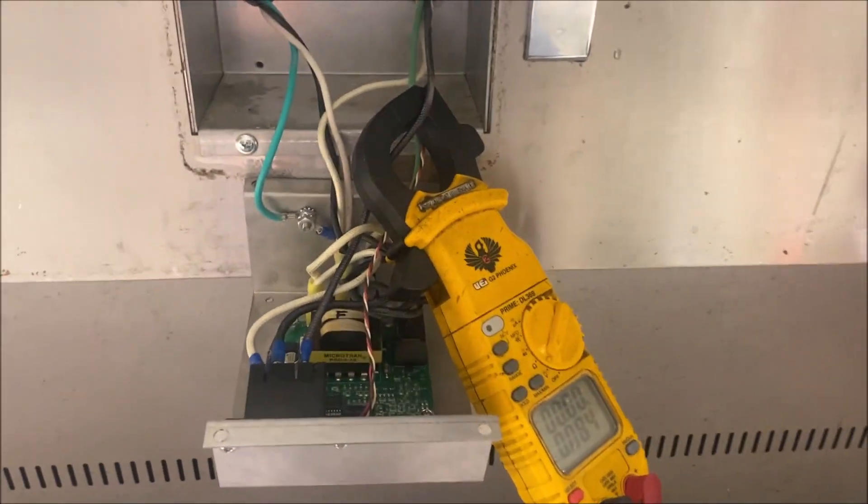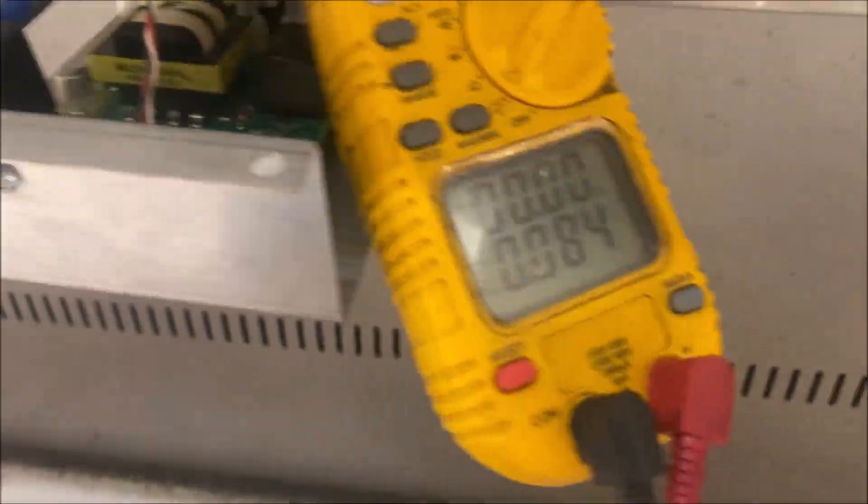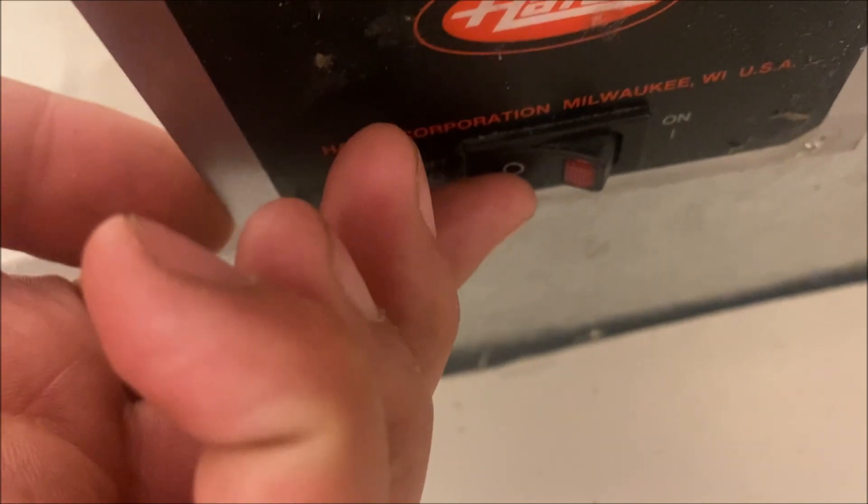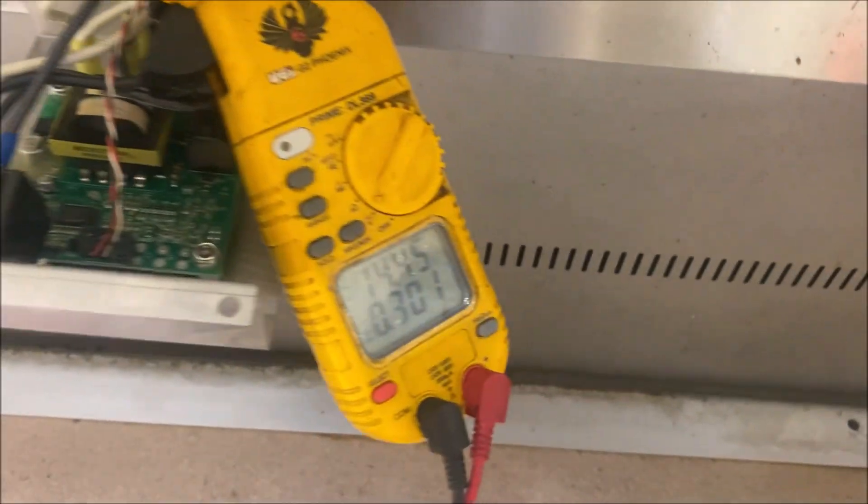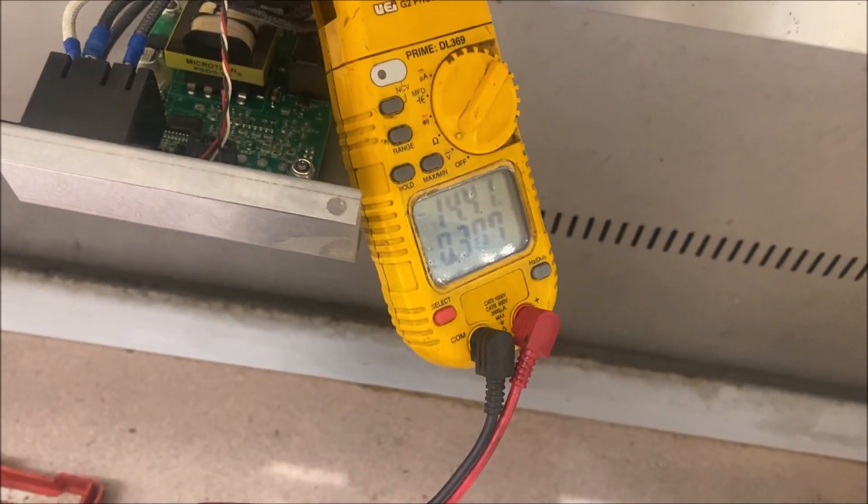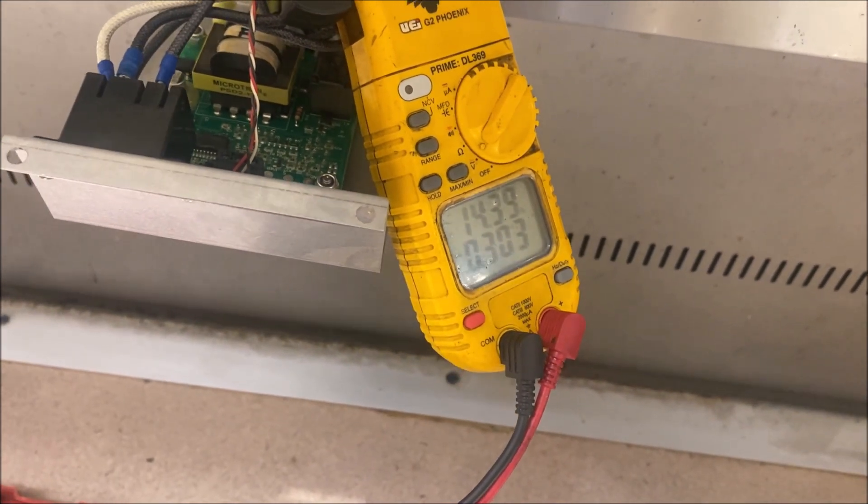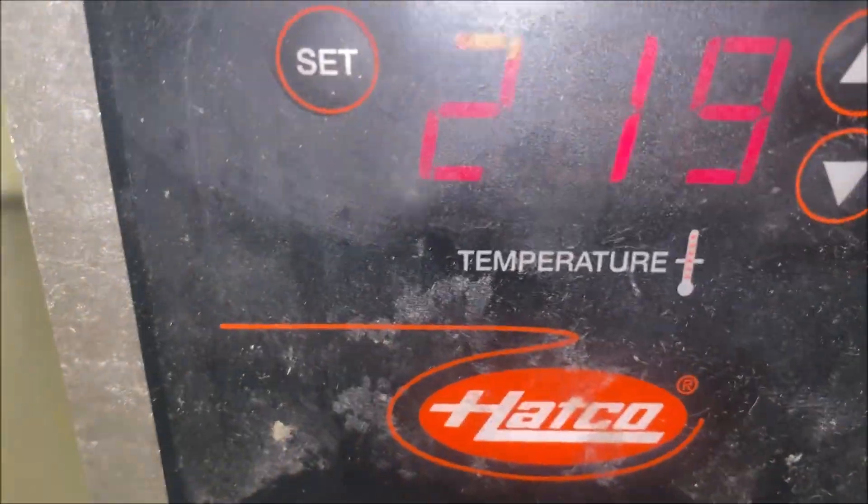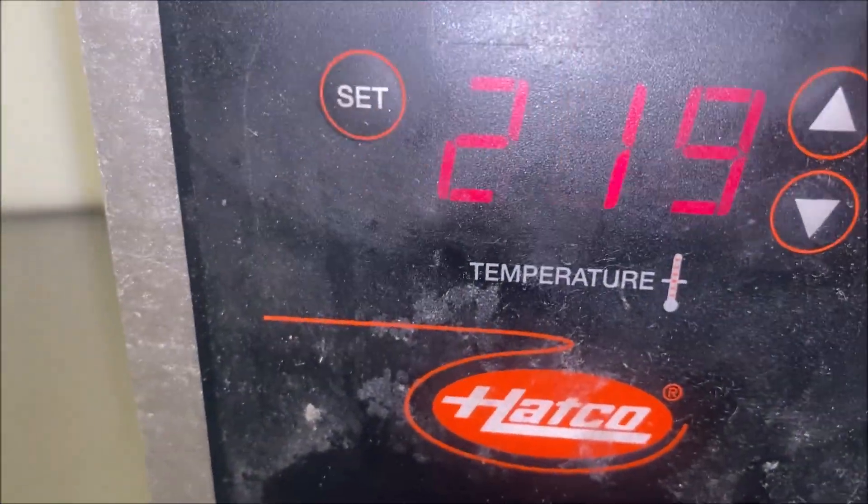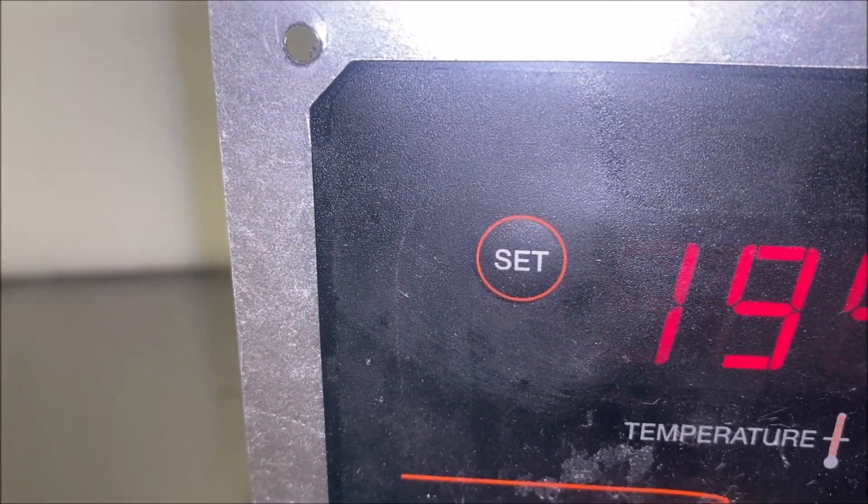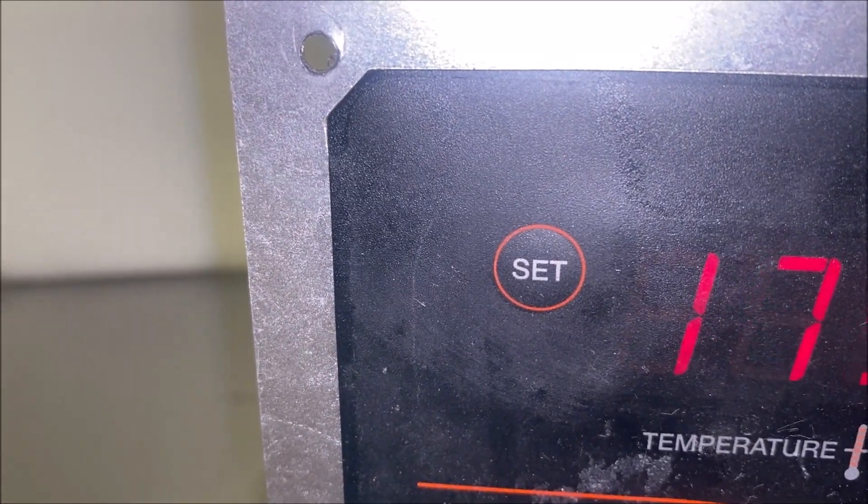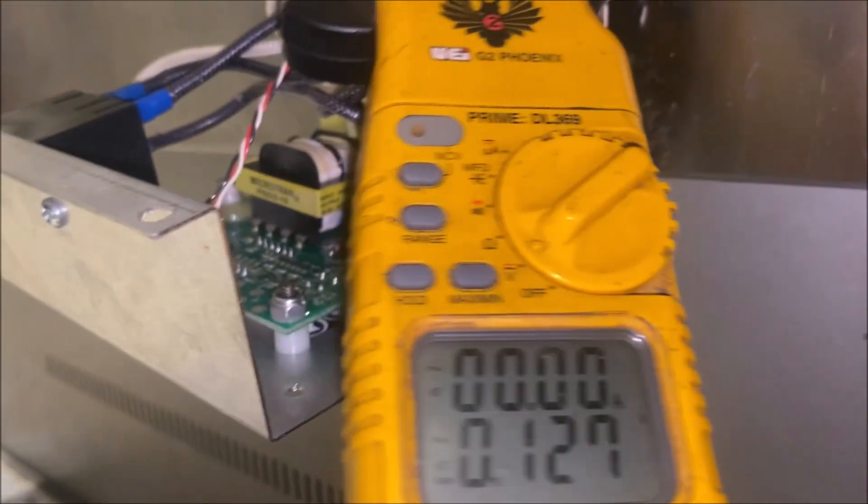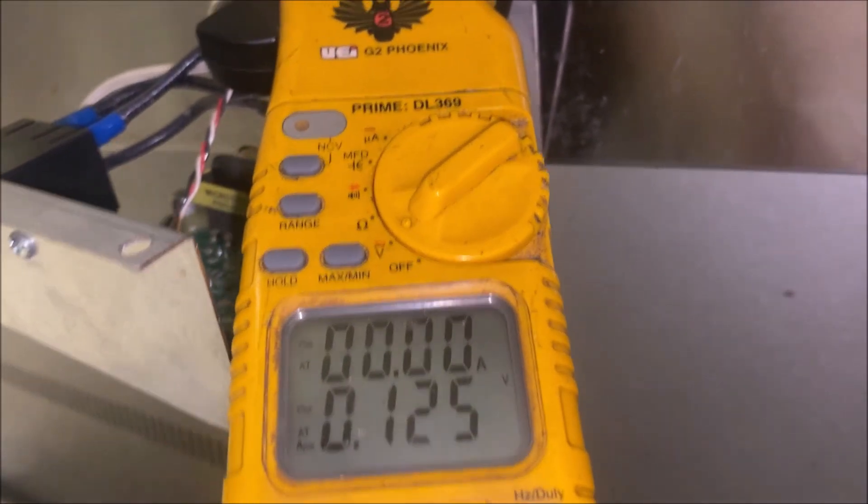Let's go ahead here. I put a new relay in. As you can see we're getting zero amps with the switch off, which is what it should be doing. We're going to fire up the switch here. Let's just make sure that we do get amperage and we do, we have 14 amps so that's good. Now the last thing we want to make sure is that the unit is going to shut off. So what we're going to do here is lower the set point to below the current temperature, and then the relay should open and then we should lose our amp draw. And as you can see here we lost our amp draw, so the relay is now opening as it should be.